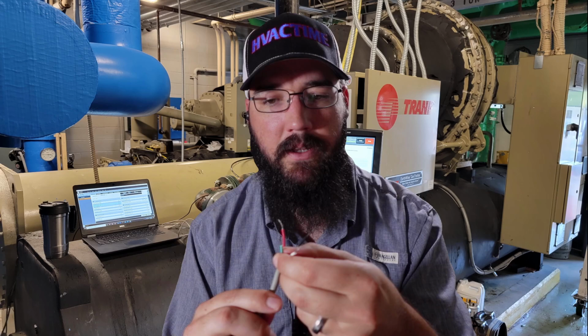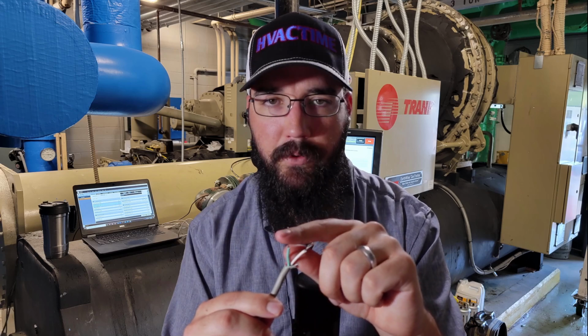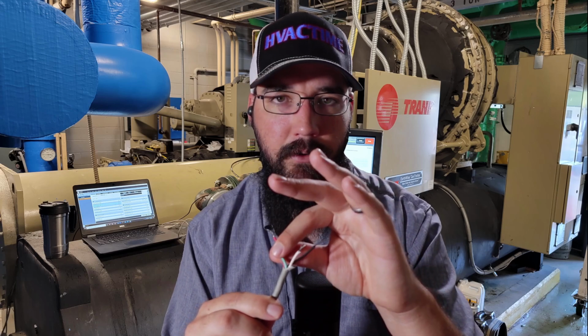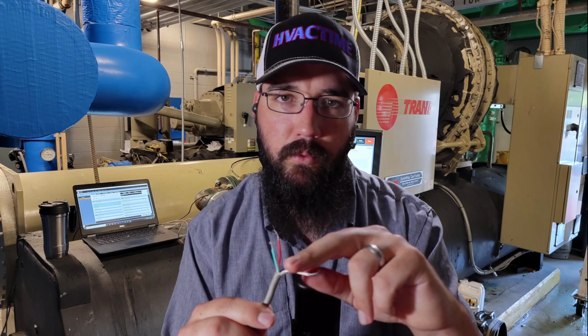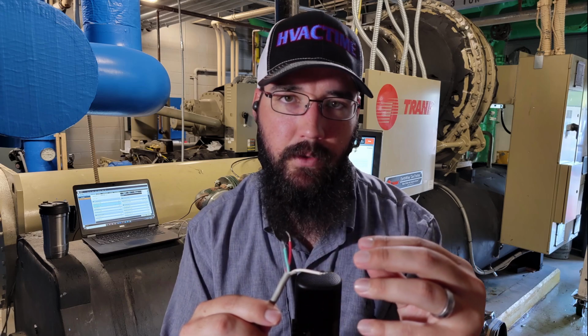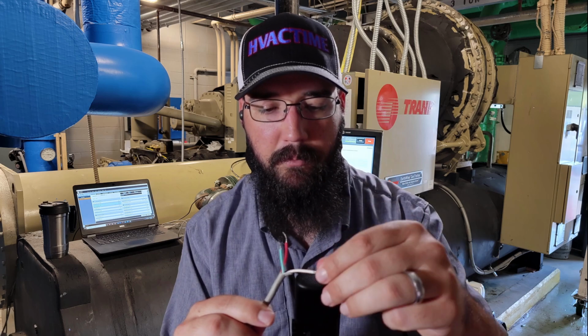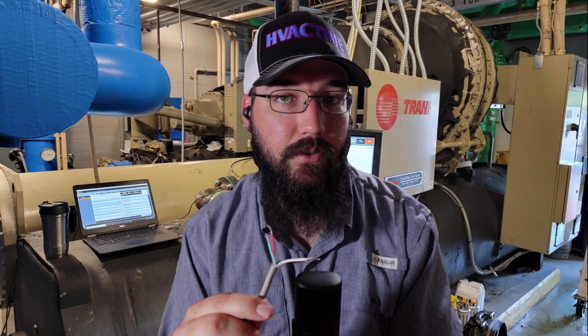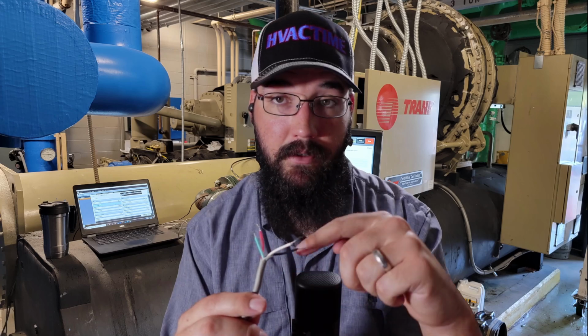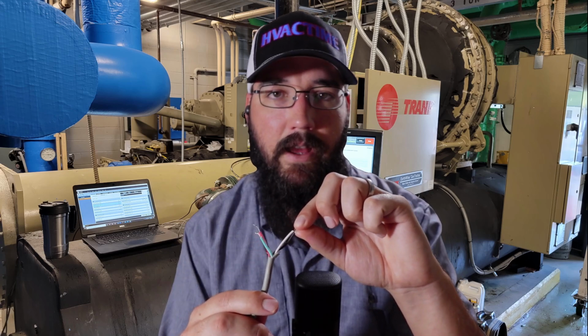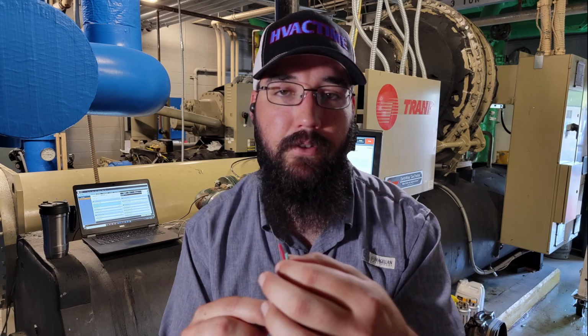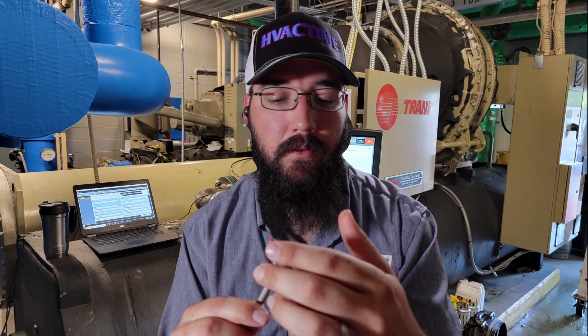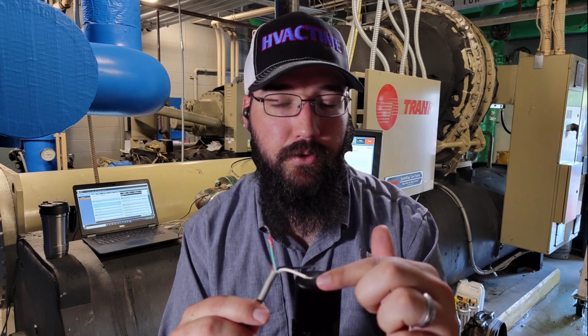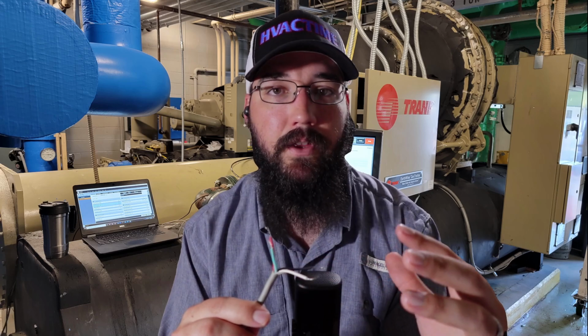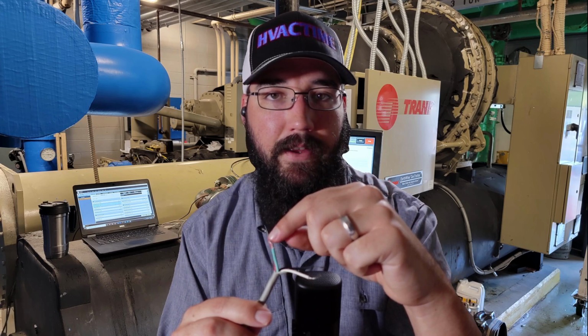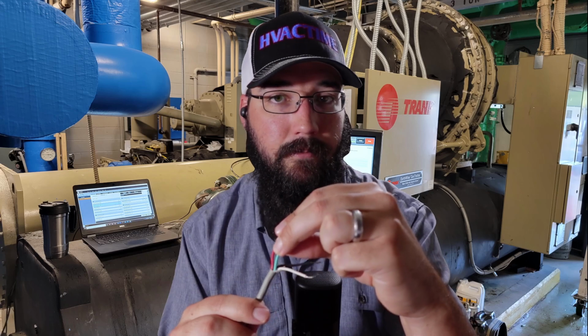Now, that also means that in a 4-wire, these other two coils don't intersect at all. So between the red and green coil and the black and white coil, there will be no electrical connection. I have to be careful with how I term that, but they're not connected electrically, and there's nothing connected to ground either. So for the failures that can happen, in this particular case, this black and white has 50 ohms across, but the red to green has OL. Nothing to ground, none of these wires to ground, and there's no internal short. So red and green to black or white, nothing is connected there. But the stator failed on the red and green winding.